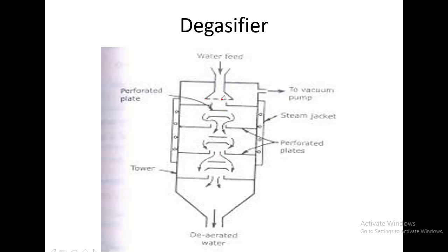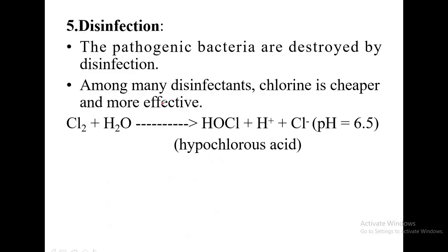These perforated plates are supported by steam jackets. So the plates are quite hot, and as a result, because of the high temperature and large surface area, the dissolved gases, if any, get completely stripped off, and all the gases are completely removed by the vacuum pump. Whatever water comes down here is absolutely free from dissolved gases.